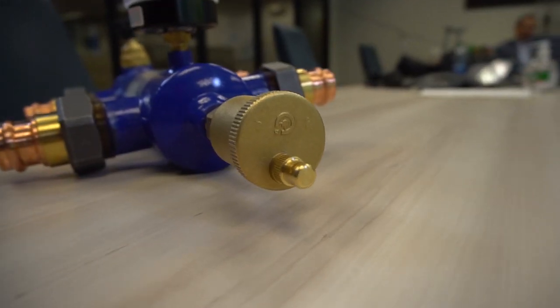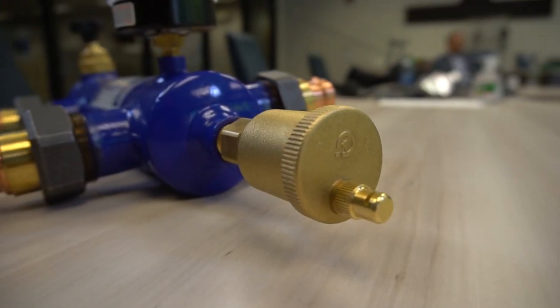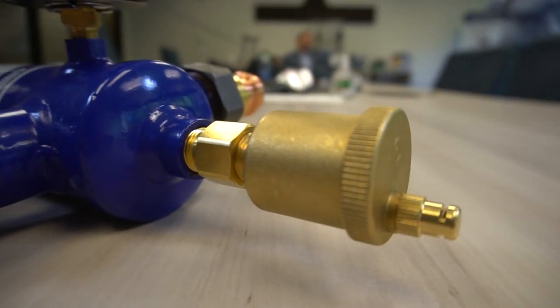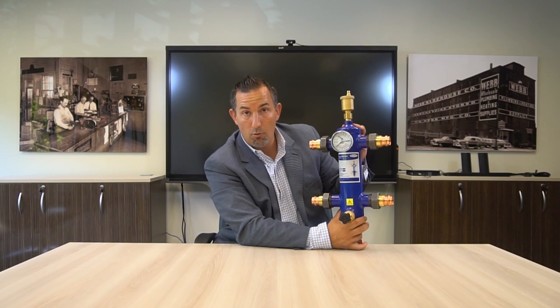Next thing I want to talk about is stainless steel coalescing air elimination. You'll see this half inch air eliminator on the top. We have a stainless steel coalescing media that's designed to eliminate all the air in the system and also all the micro bubbles in the system. It's placed at the top of the unit, which is where the air resides.